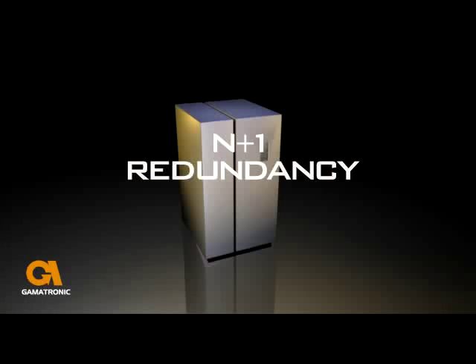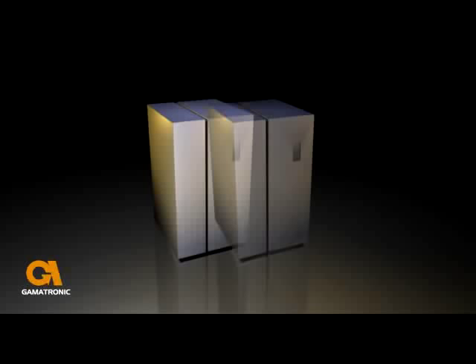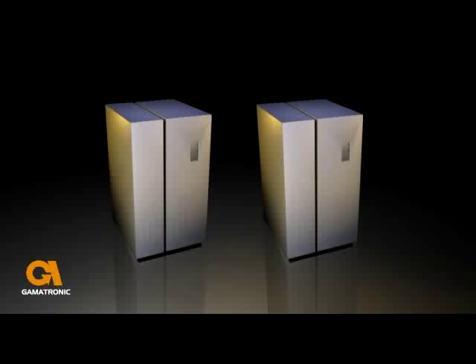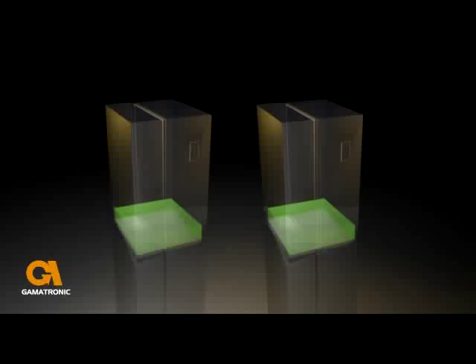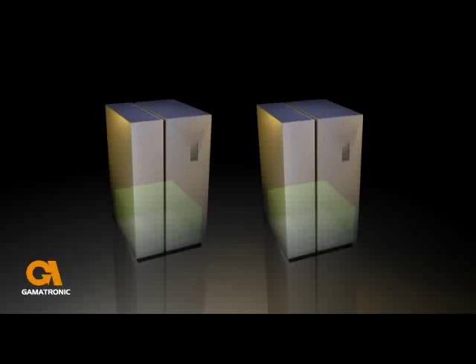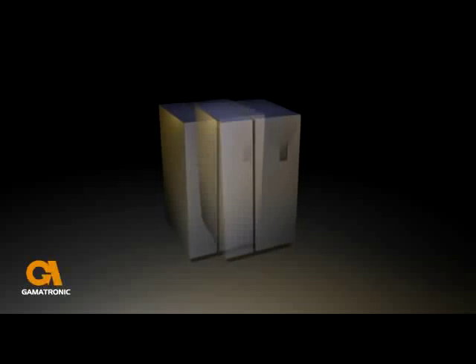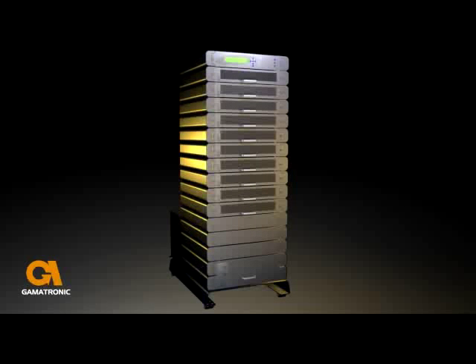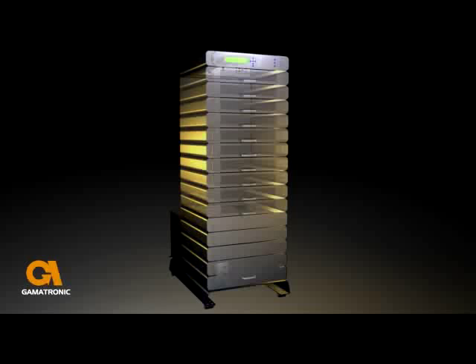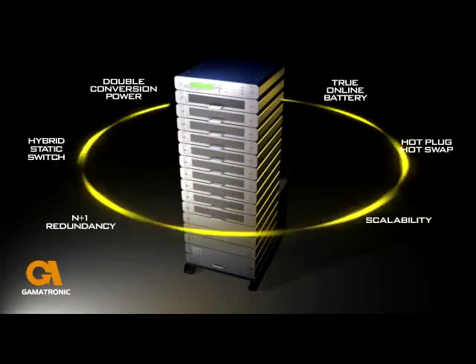The Power Plus delivers incremental redundancy at lower cost than conventional systems. In a typical system, redundancy is achieved by deploying two or more larger UPS units with the capacity to carry the total load. This results in significant unused capacity and lowered efficiency of all the units in the system. With the Power Plus, modular redundancy can take place in 10 kVA increments, so all units function at higher capacity. This results in higher efficiency, 94%, for the entire system. The result is lower heat and reduced cooling costs, and that can add up to significant savings in data center overhead.